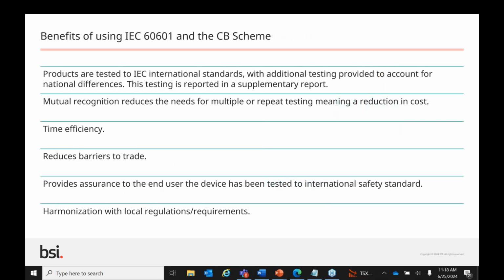So what are the benefits of using IEC 60601 and the CB scheme? Well, first of all, there's a whole piece around national differences. So member countries need to publish their national differences, which are available on the IEC website. In countries where national standards are not yet completely based on IEC international standards, declared national differences are considered. So national differences might include the requirement to demonstrate a product complies with factors specific to that country.